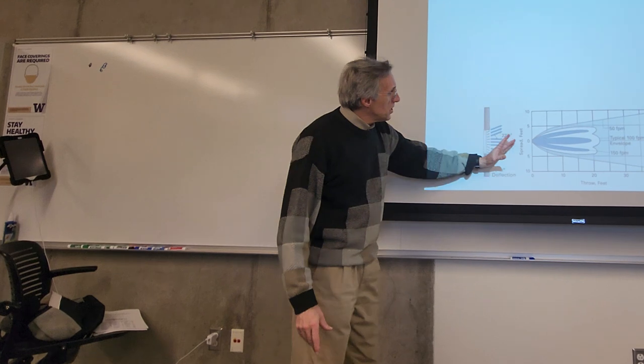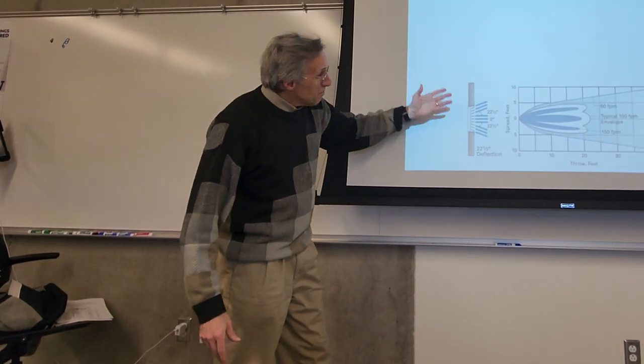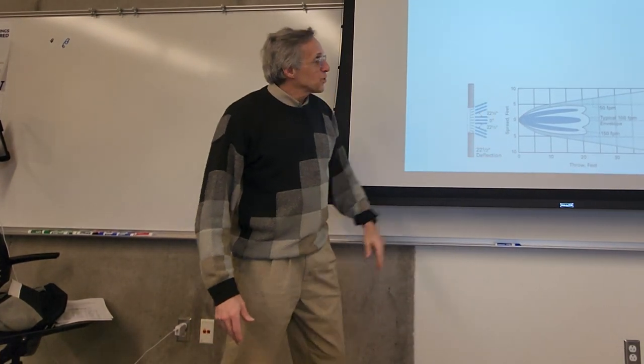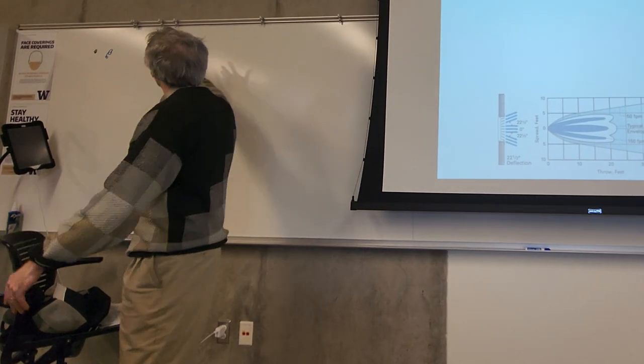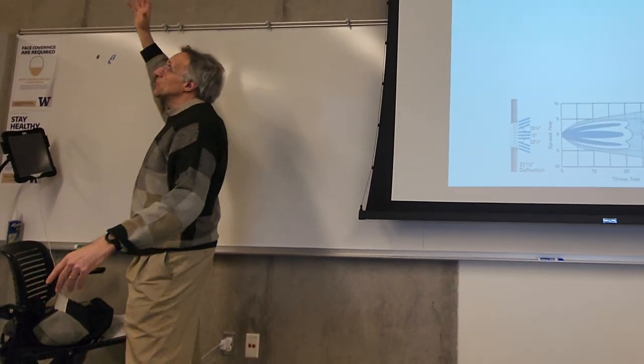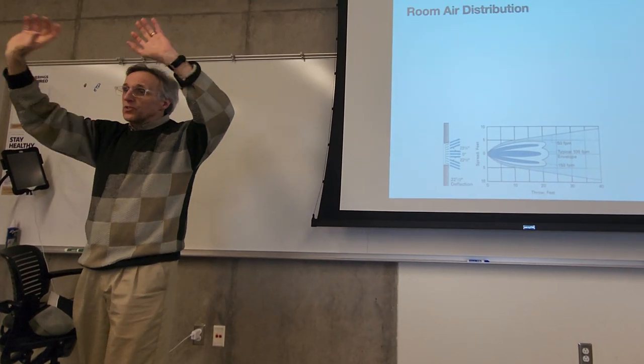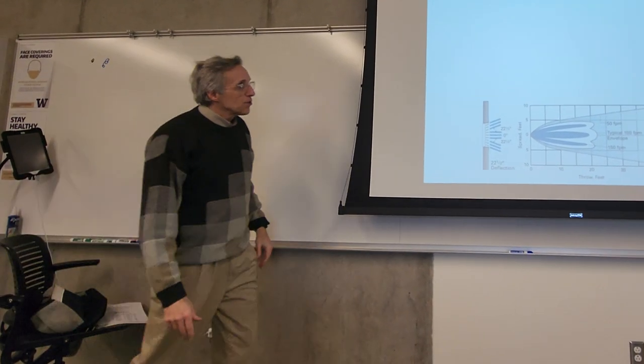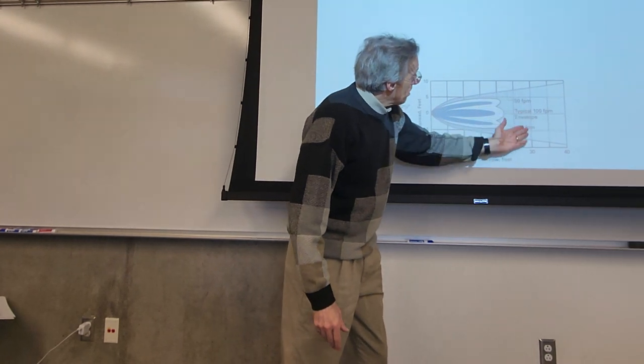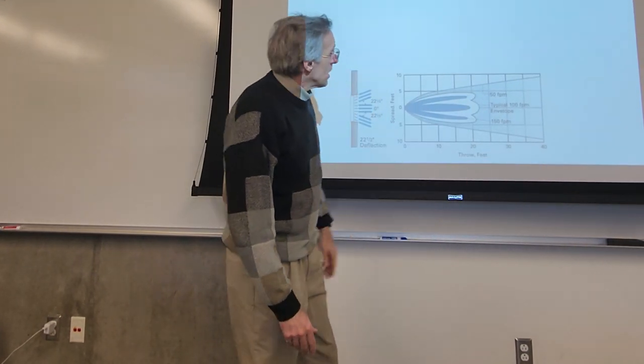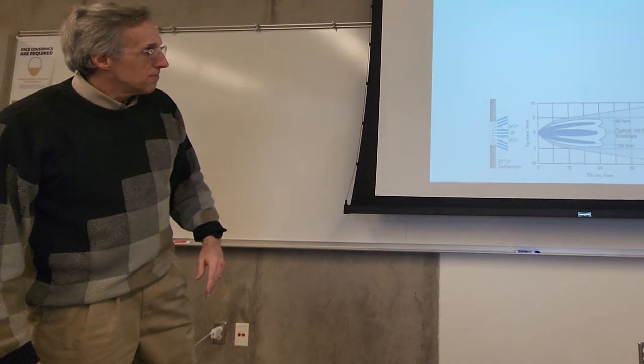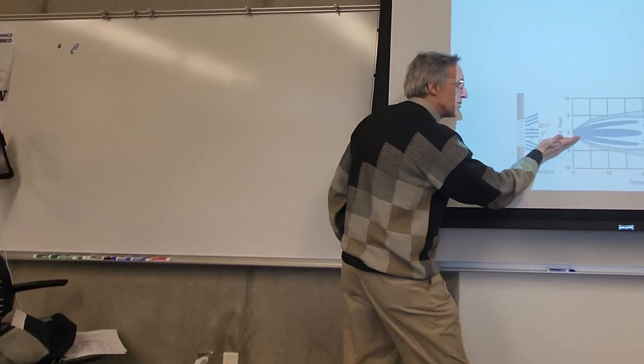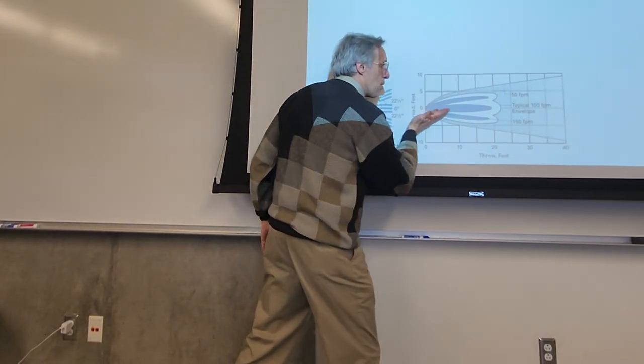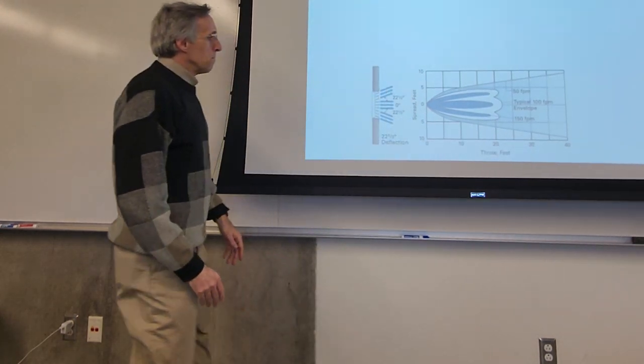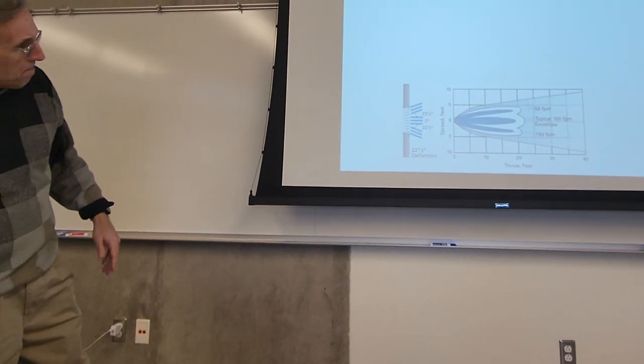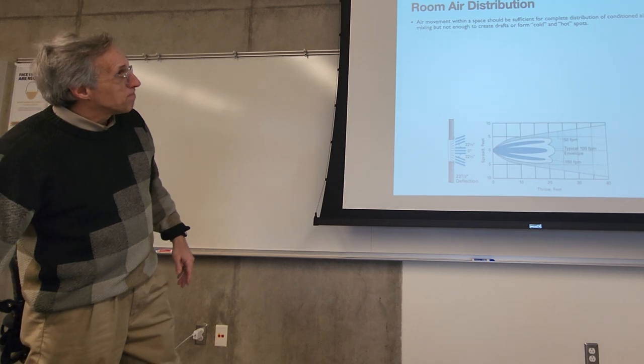So room air distribution is very important, and we've got a whole section of the ASHRAE handbook just on the mechanical design of the registers and how you want to steer the air. There's a fluid mechanics around that that's kind of interesting. So 50 feet per minute at the envelope, 100 feet per minute in the middle there. And we talk about throw, you know, how far does this air go before it drops? It'll go out and it'll start to drop off. And there's some guidelines for that.